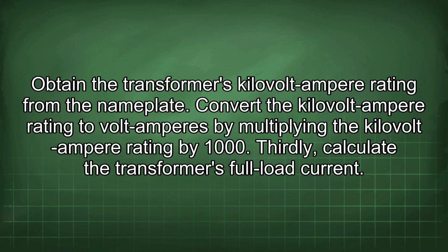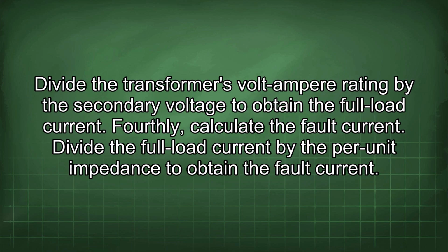Convert the kilovolt-ampere rating to volt-amperes by multiplying the kilovolt-ampere rating by 1000. Thirdly, calculate the transformer's full load current. Divide the transformer's volt-ampere rating by the secondary voltage to obtain the full load current.